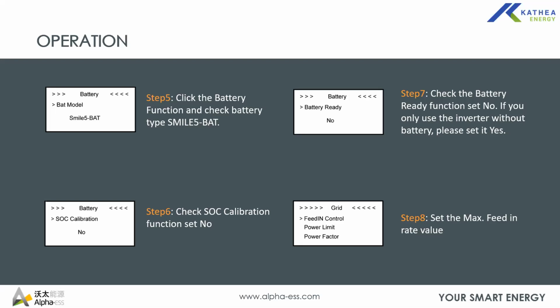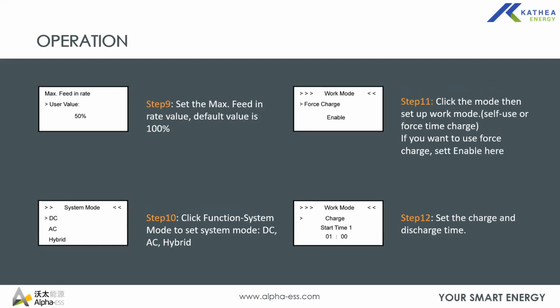By default, it's 70%. If you are not to feed back to the grid, then you would need to set it to 0. If you wish to feed maximum power to the grid, then you need to set it to 100%. Then it will feed 5 kilowatt to the grid. And for all other percentages, simply calculate that percentage of 5 kilowatt. So you can set the maximum feed in rate user value to any preferred value.